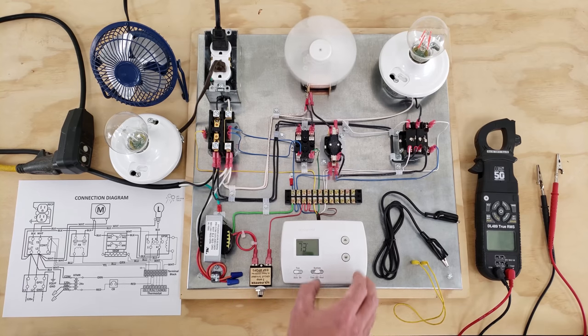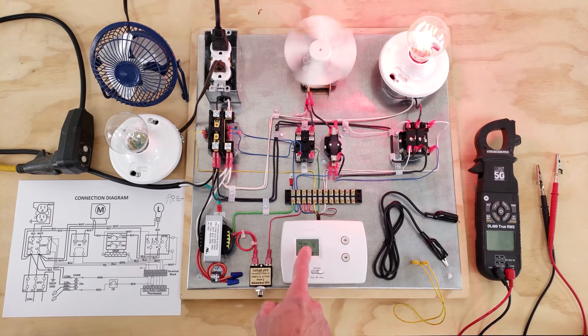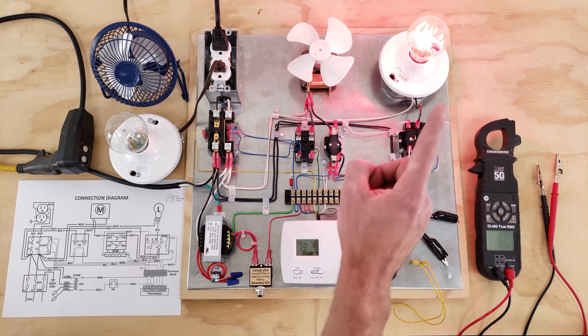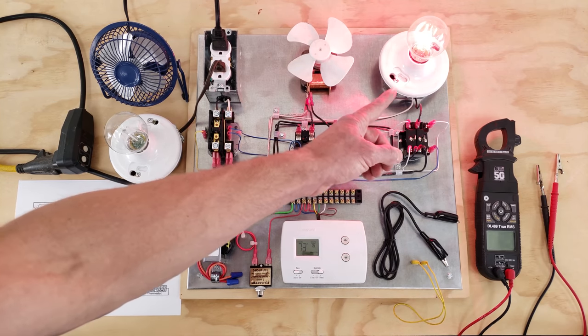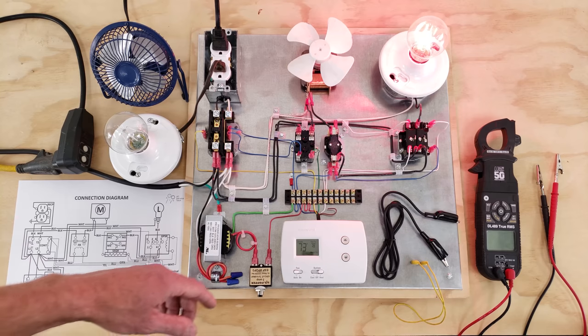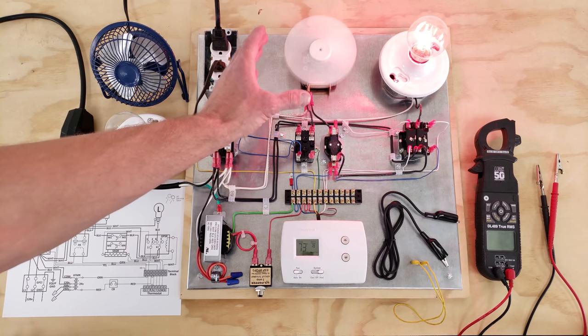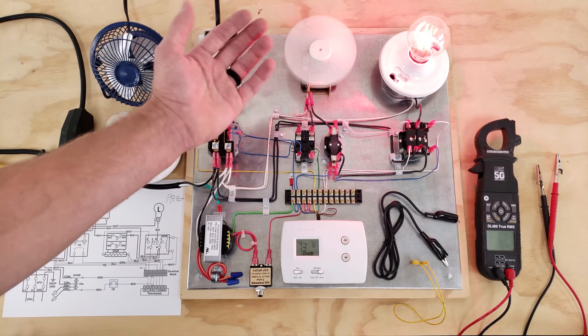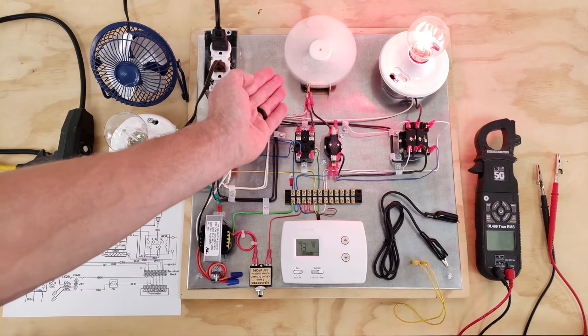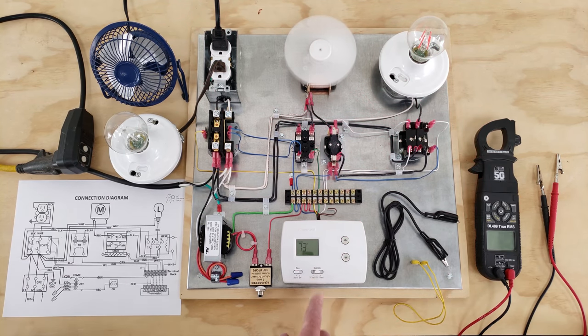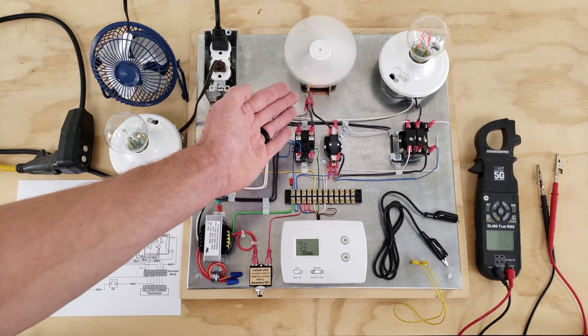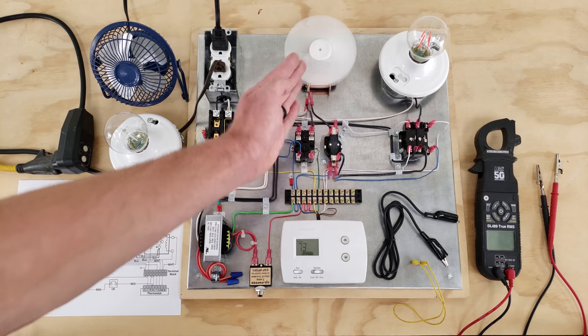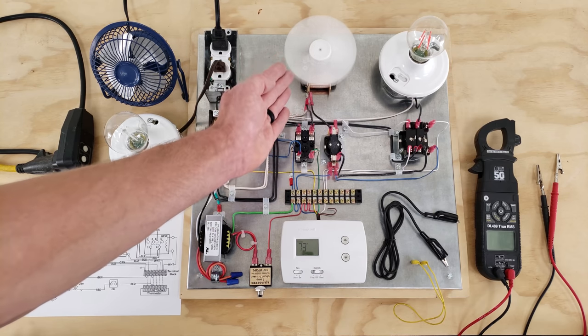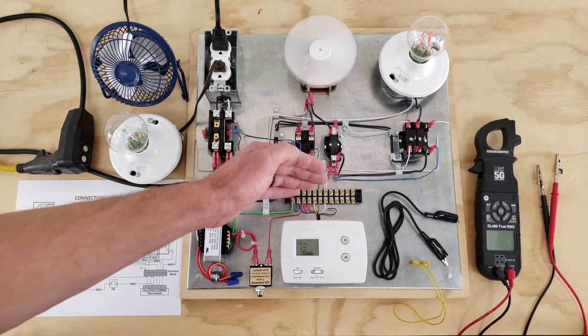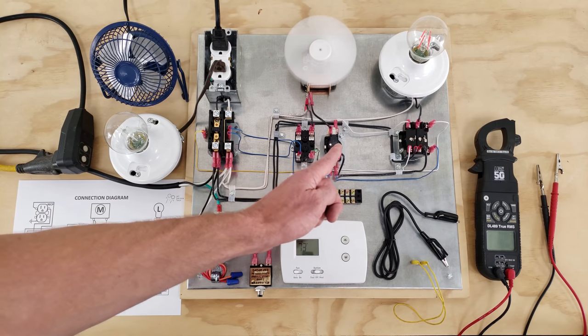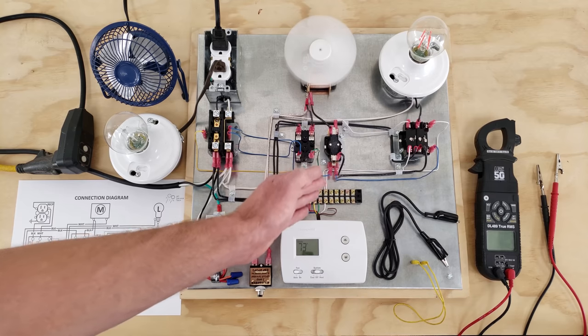So that's our fan, and then for our heat we're going to turn our temperature up to 78. It's 73 in this building right now, and you see that our light bulb is lit. This is actually red right now. You could spray paint that red, but what's happening is we're utilizing our sequencer right here to have a timed powering of a fan. So that would signify basically that our heat exchanger is warmed up and now our fan is running. And say you want to turn the heat off, our fan does not turn off right away in a gas furnace. What happens is our gas valve shuts off, but our fan continues to run, and it's basically lowering the temperature at the heat exchanger area. And so there's already heat there, and so you want to be able to blow that heat through the building. So that's why we use a sequencer in order to have a timed powering of that fan.